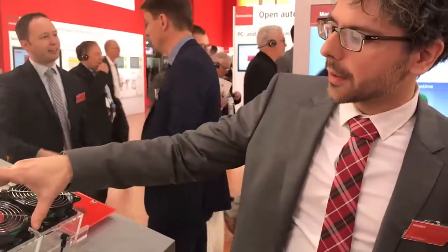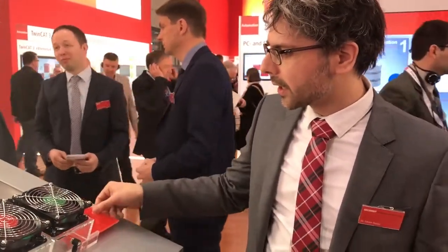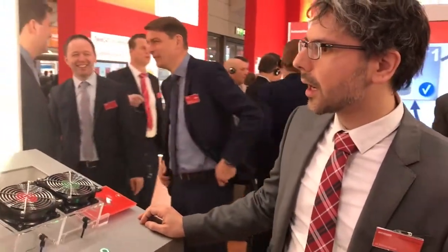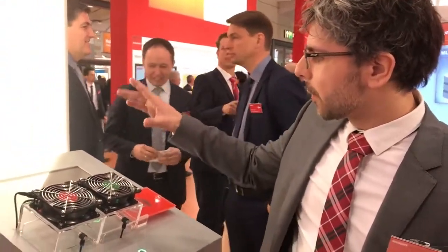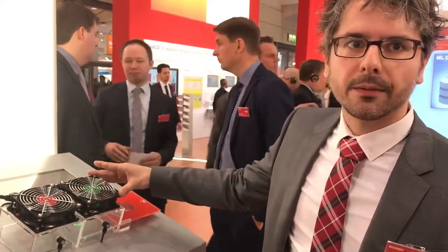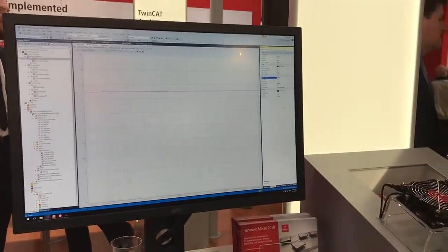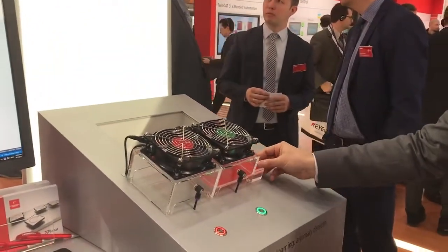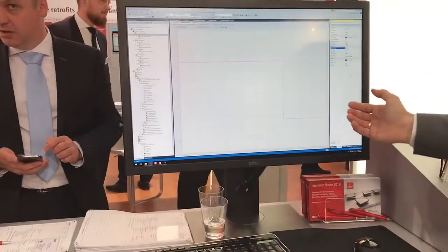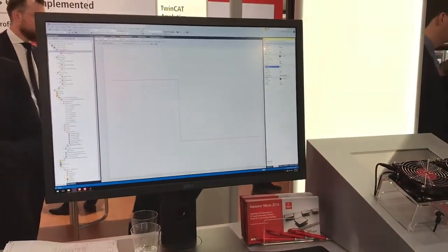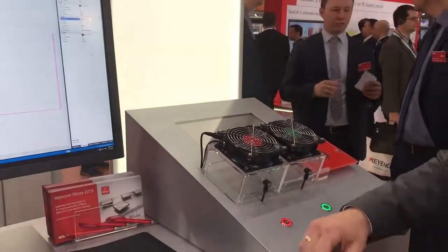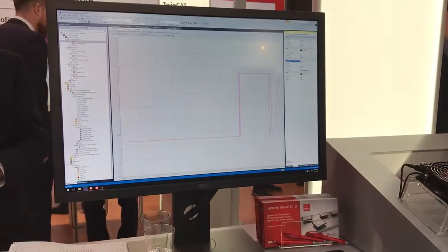non-damaged fan and damaged fan, and I can also manipulate here the air pressure flow. And what we can see then in the result of the graph is that once the non-damaged fan is running, everything is okay, so the support vector machine knows this data, everything is classified as 1, which means everything is fine. And now I just close the clamp here, and immediately our algorithm says, well, something is different, and I open it again, and I come up again, okay, it's good again.